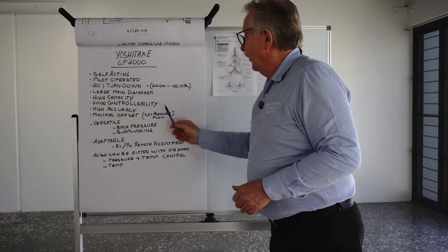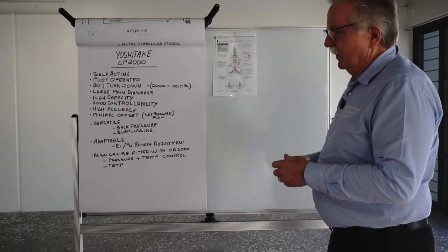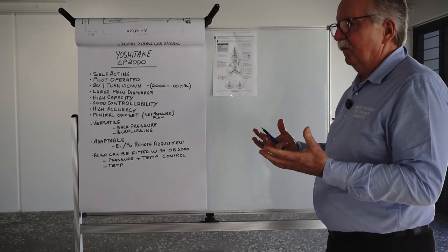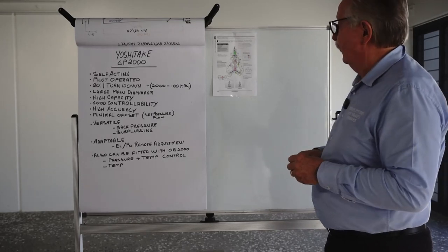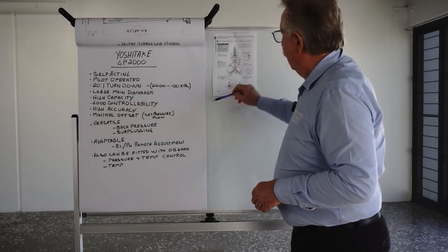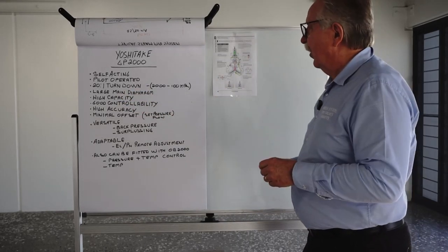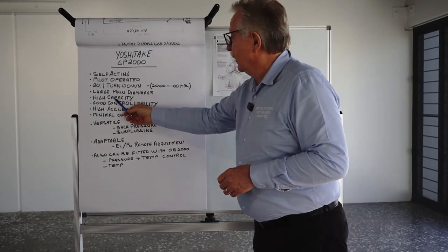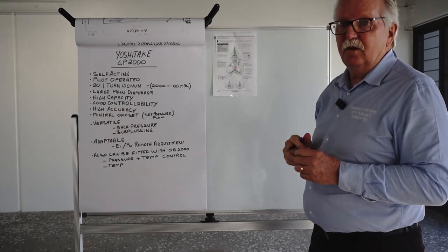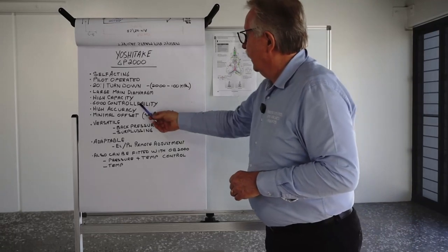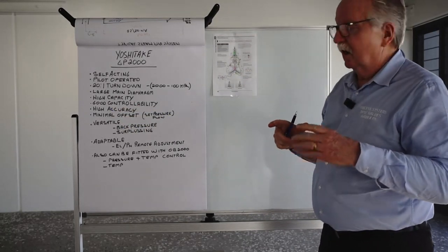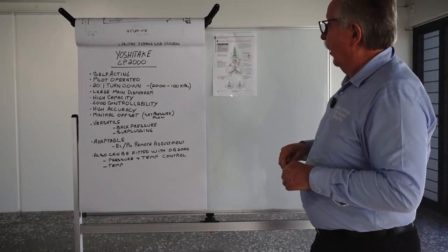The large main diaphragm. We spoke about that. And you need that to get controllability over the valve. The bigger the diaphragm. The better the controllability over your downstream set pressure. Also able to open bigger valves. So you get higher capacity. All GP2000s have a high capacity for their size. And they have good controllability. Mainly because of that larger diaphragm. They are highly accurate. Once they are set.